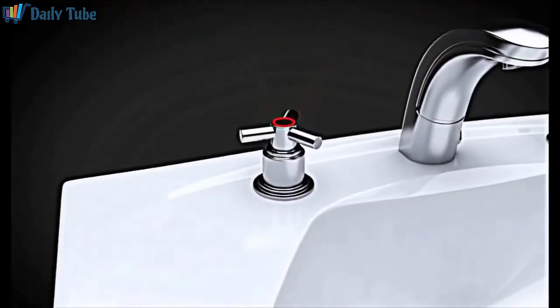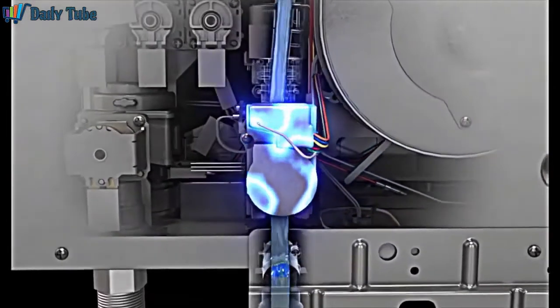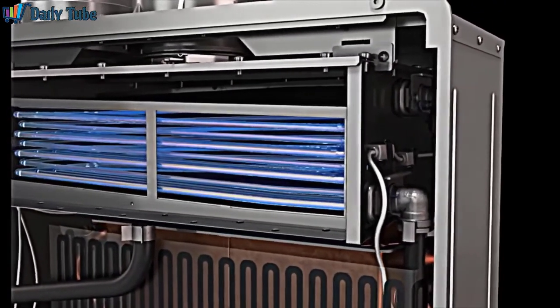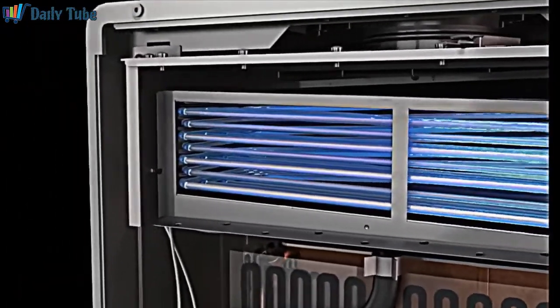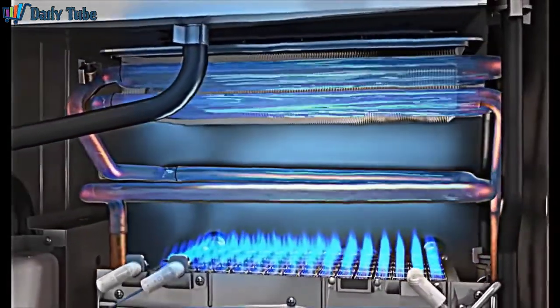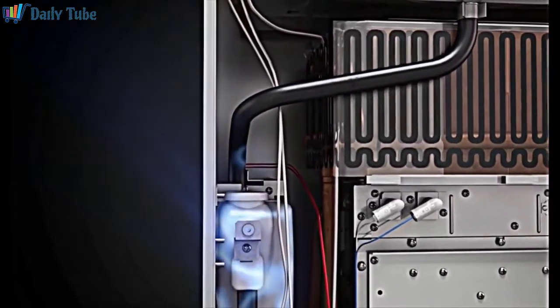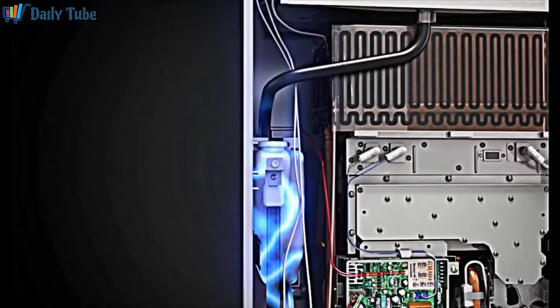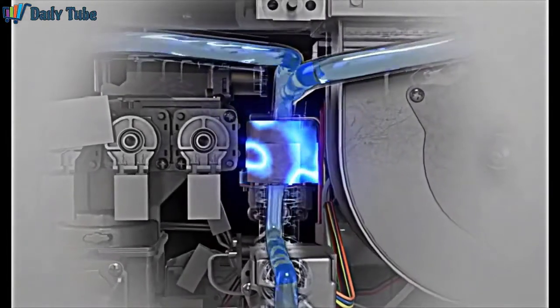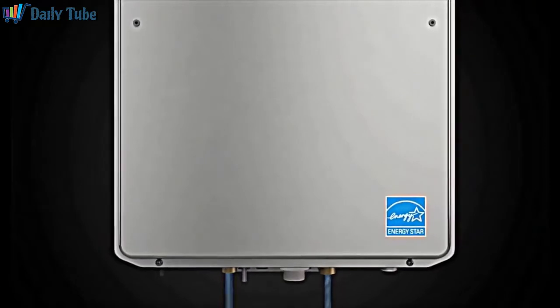When a homeowner turns on a hot water tap, cold water enters the water heater. The flow sensor inside the water control valve activates the gas burner, which warms the heat exchanger. The incoming cold water first passes through the secondary stainless steel heat exchanger at the top of the unit. Then the preheated water circulates through the primary copper heat exchanger at the bottom and is rapidly heated to temperature. During this process, condensate is produced within the tankless unit. In the Prestige series model, this condensate is directed to a neutralization chamber that eliminates acidity so it can be disposed of in any common household drain. The heated water is then balanced by the computer-controlled water bypass valve so the hot water exiting the unit is within two degrees of the set temperature, giving the homeowner maximum efficiency and saving energy costs.